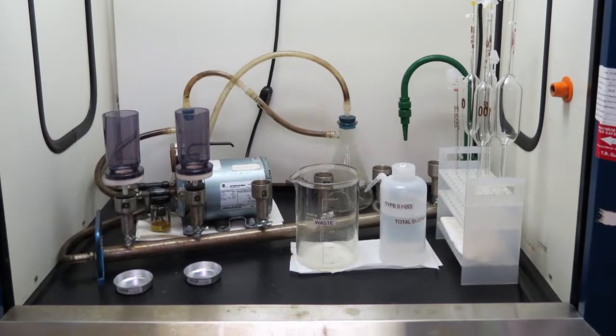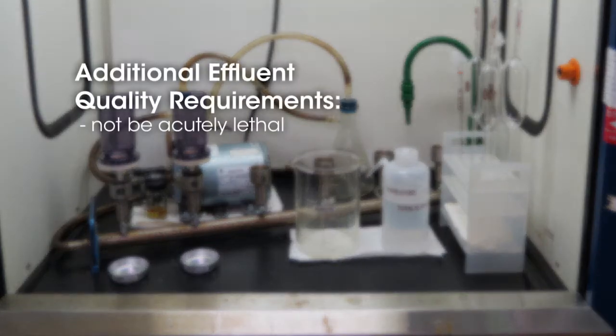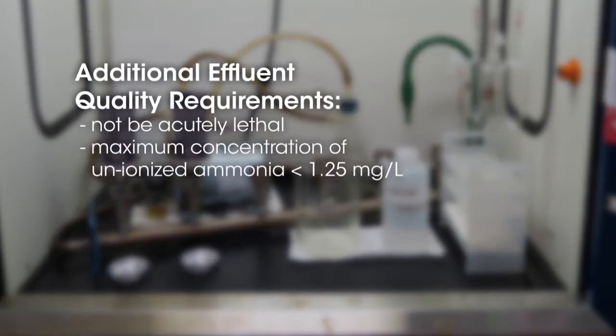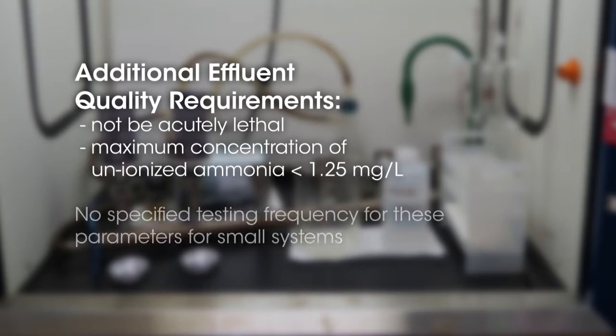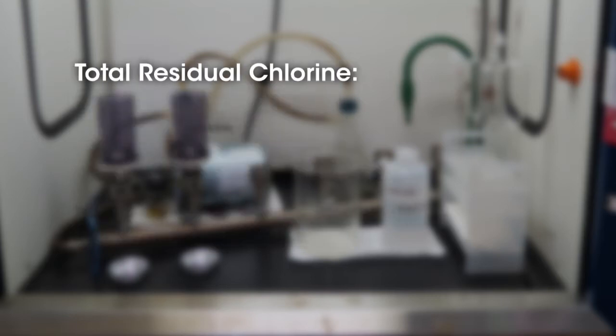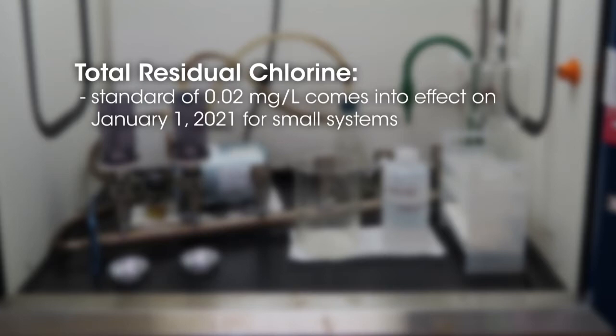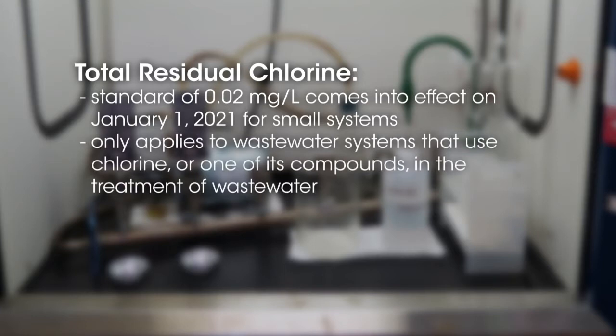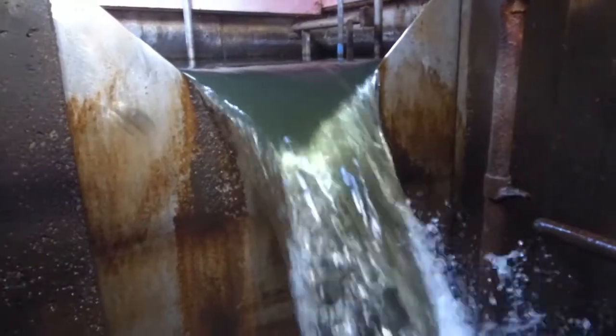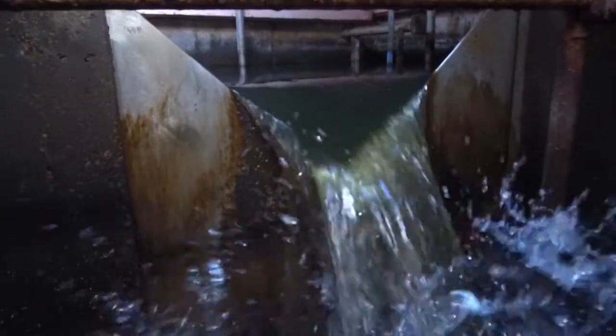Effluent discharged from the final discharge point must not be acutely lethal and must have a maximum concentration of unionized ammonia of less than 1.25 milligrams per liter. However, for small systems, there is no specified testing frequency for these parameters. For small systems, the total residual chlorine standard of 0.02 milligrams per liter comes into effect on January 1, 2021. This standard will only apply to wastewater systems that use chlorine or one of its compounds in the treatment of wastewater. Wastewater systems must also monitor the volume of effluent discharged each day.